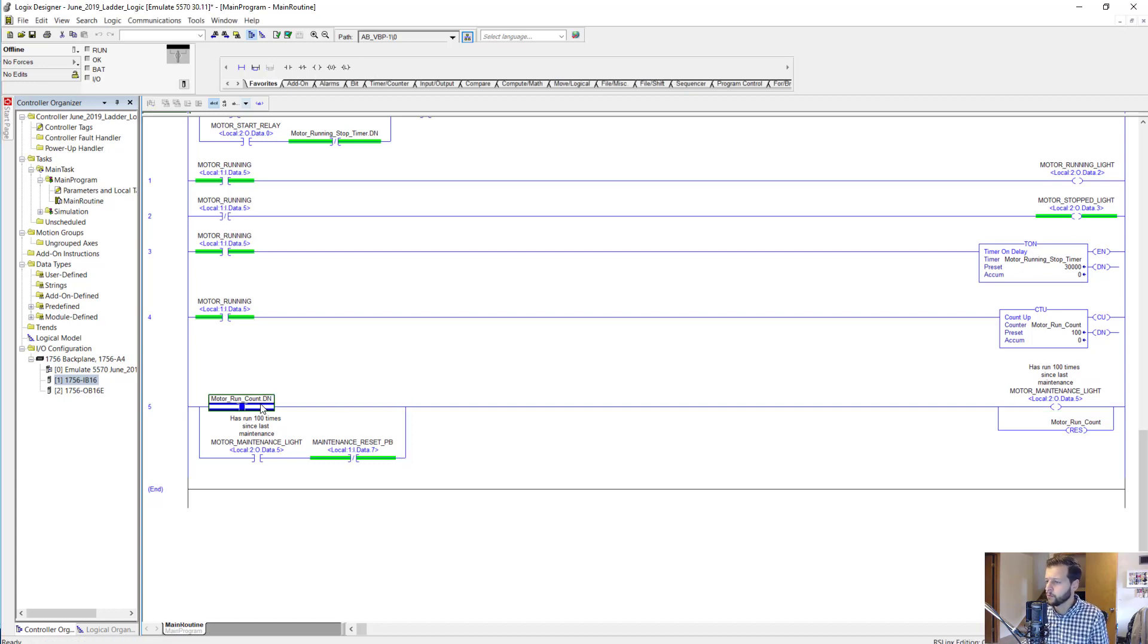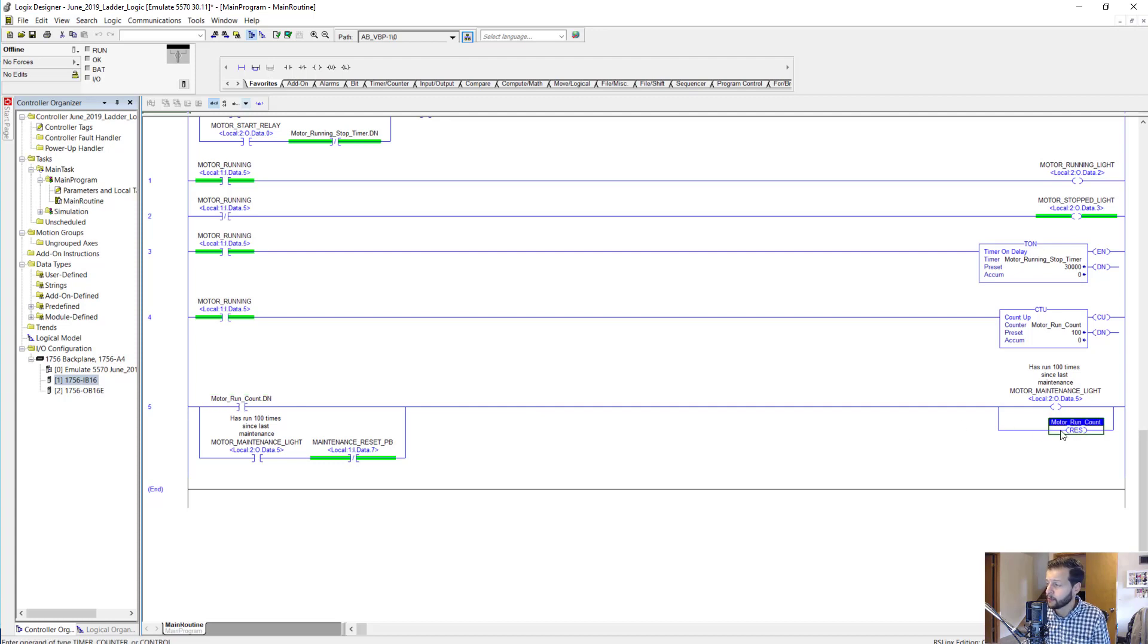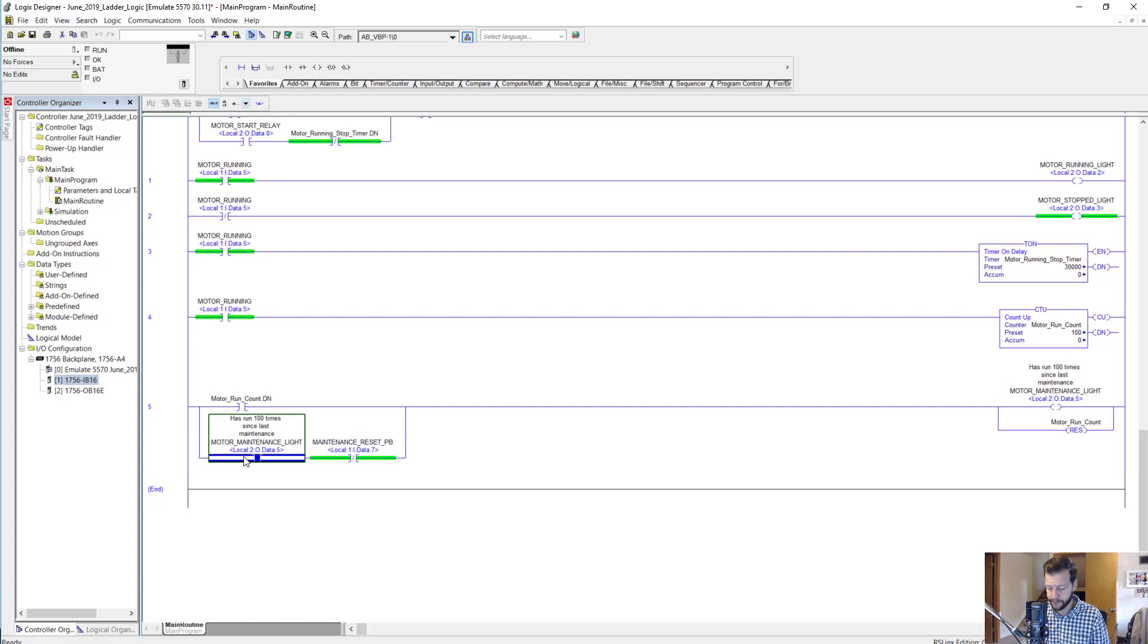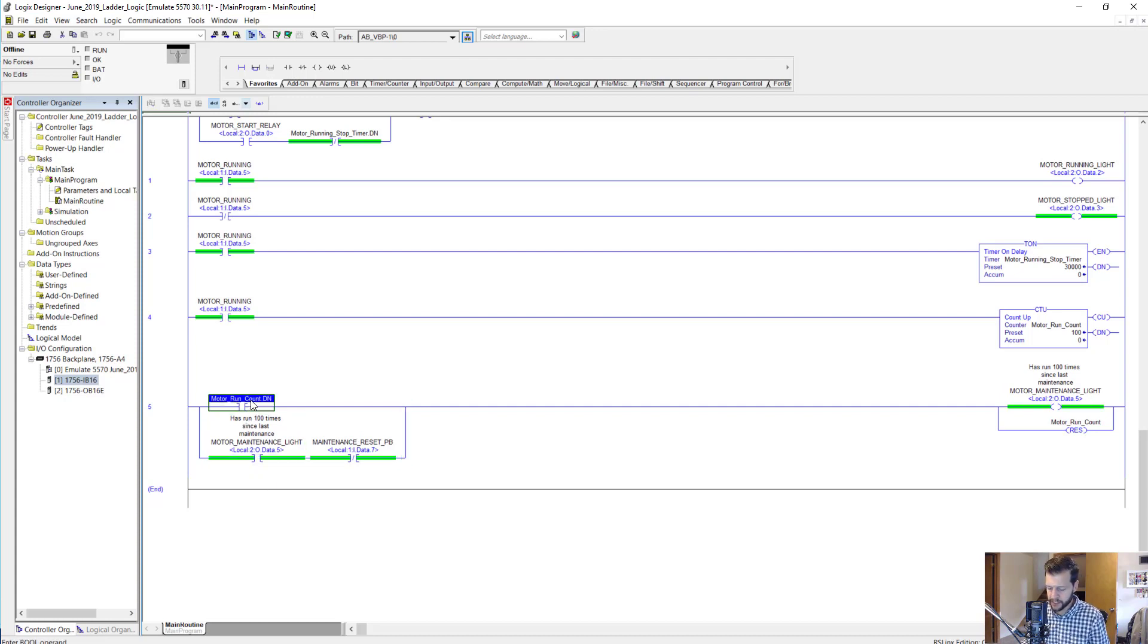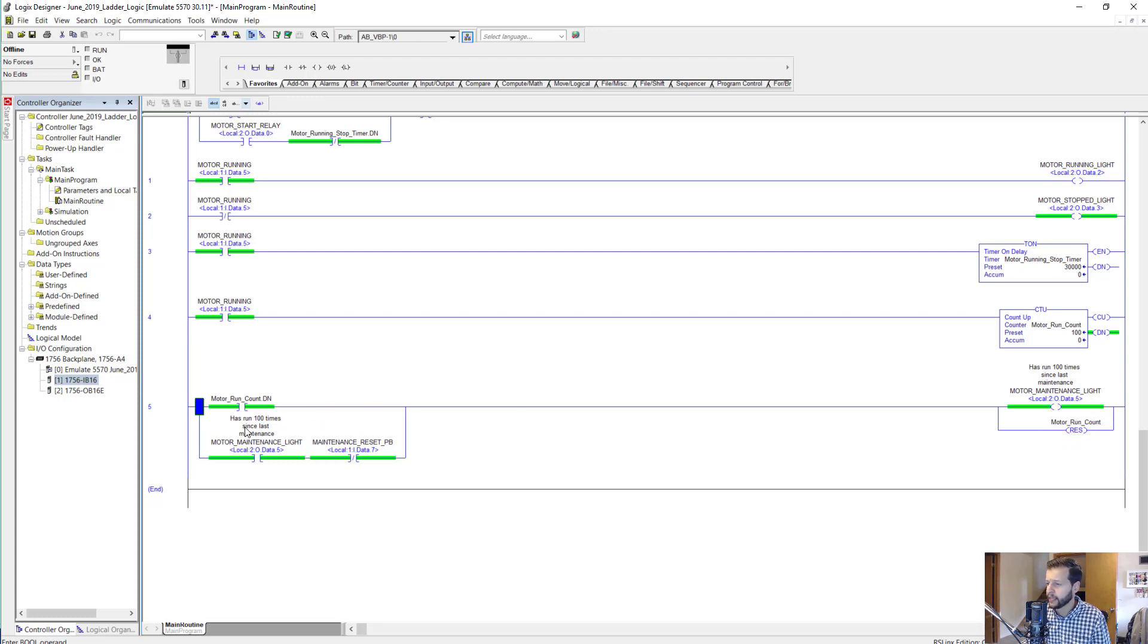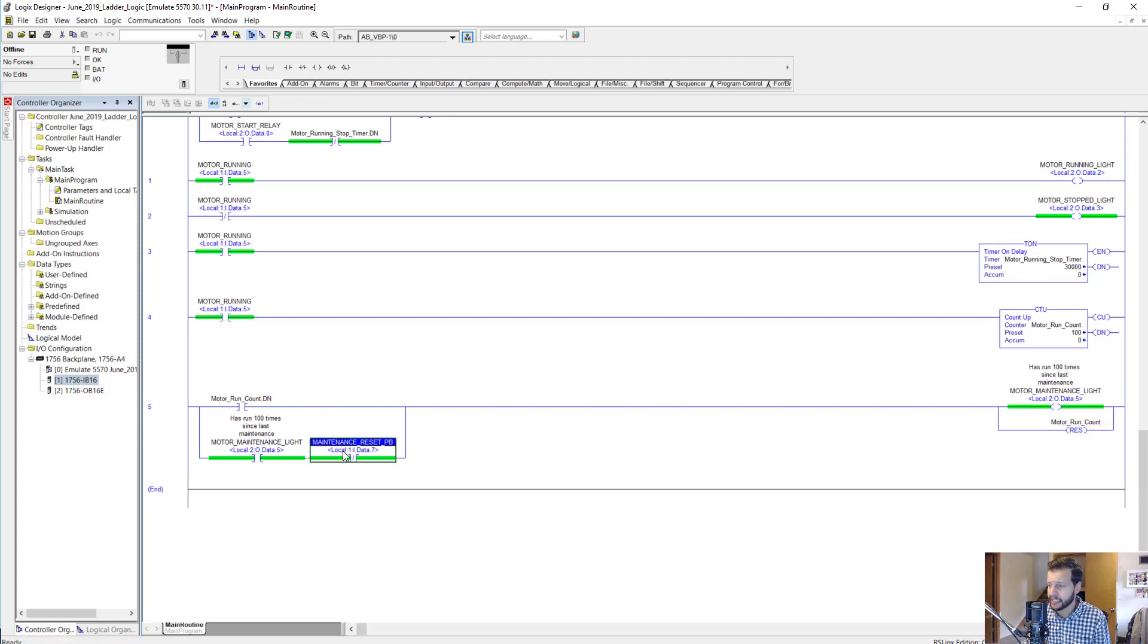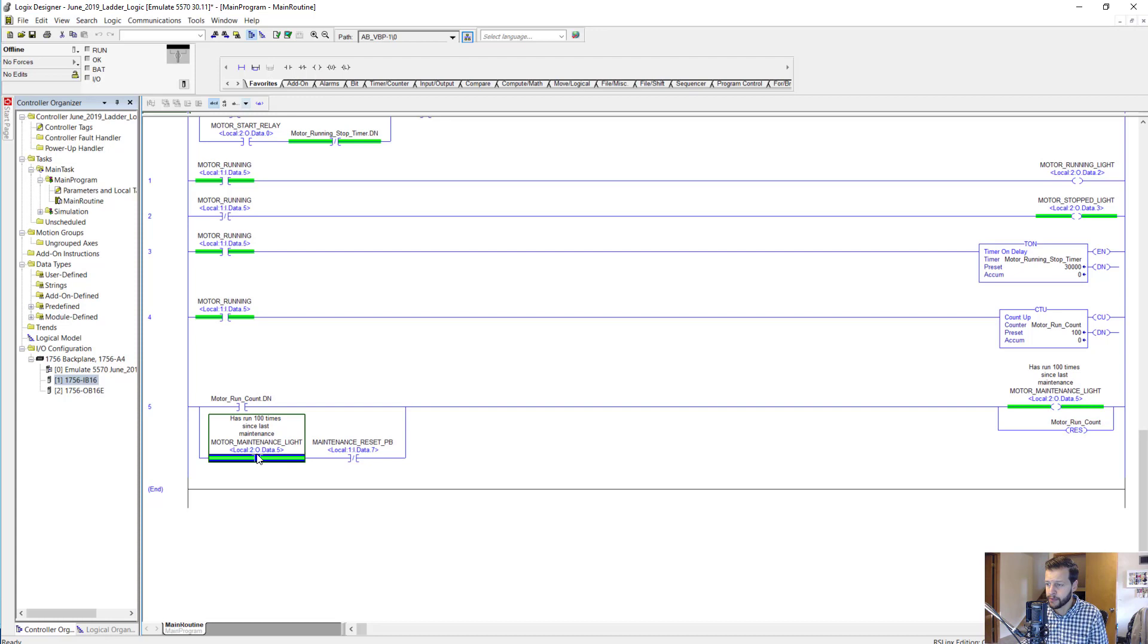What's also going on with this rung here is that we're going to turn on the motor running count RES instruction, which will reset this back to zero. This is another latch-in circuit that will latch in when this goes done. Then when this turns off because the reset has reset this back to zero, this will stay latched in until the maintenance reset push button is pressed.